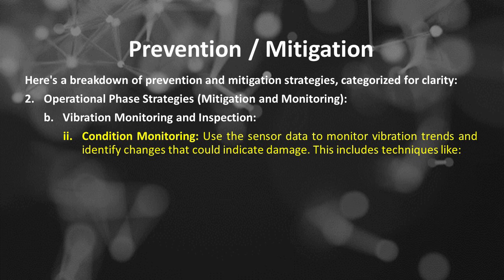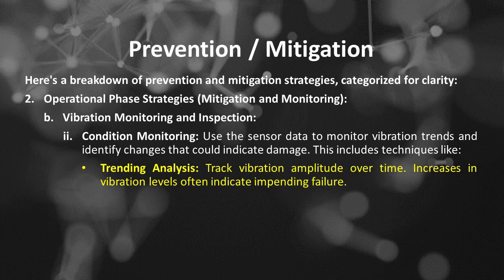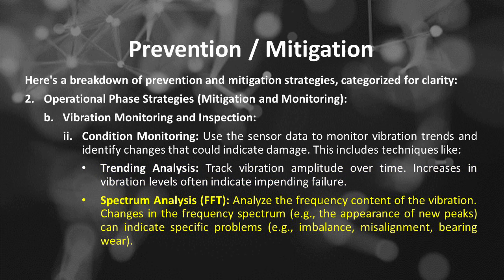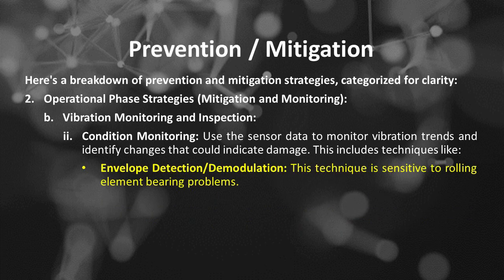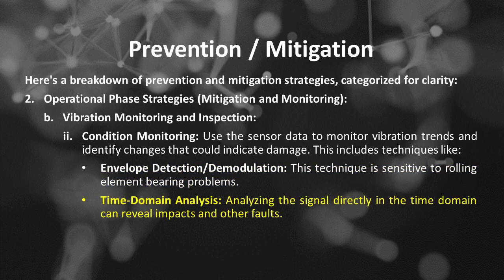This includes techniques like trending analysis: track vibration amplitude over time. Increases in vibration levels often indicate impending failure. Spectrum analysis, or FFT: analyze the frequency content of the vibration. Changes in the frequency spectrum, such as the appearance of new peaks, can indicate specific problems, such as imbalance, misalignment, bearing wear. Envelope detection or demodulation: this technique is sensitive to rolling element bearing problems. Time domain analysis: analyzing the signal directly in the time domain can reveal impacts and other faults.